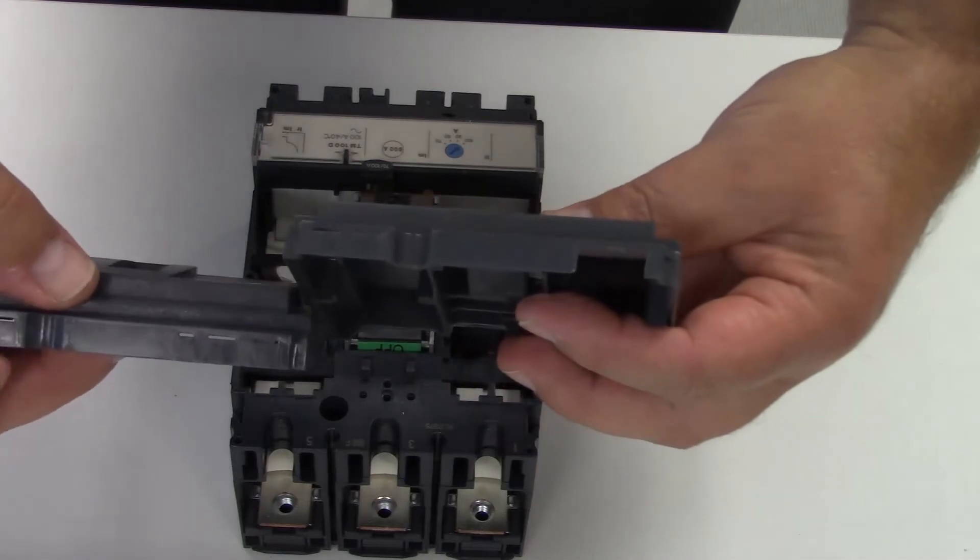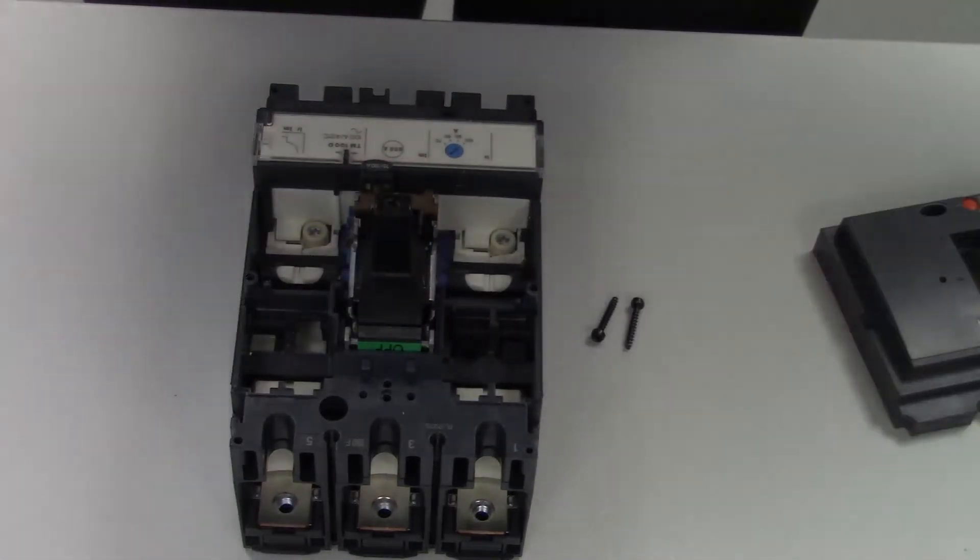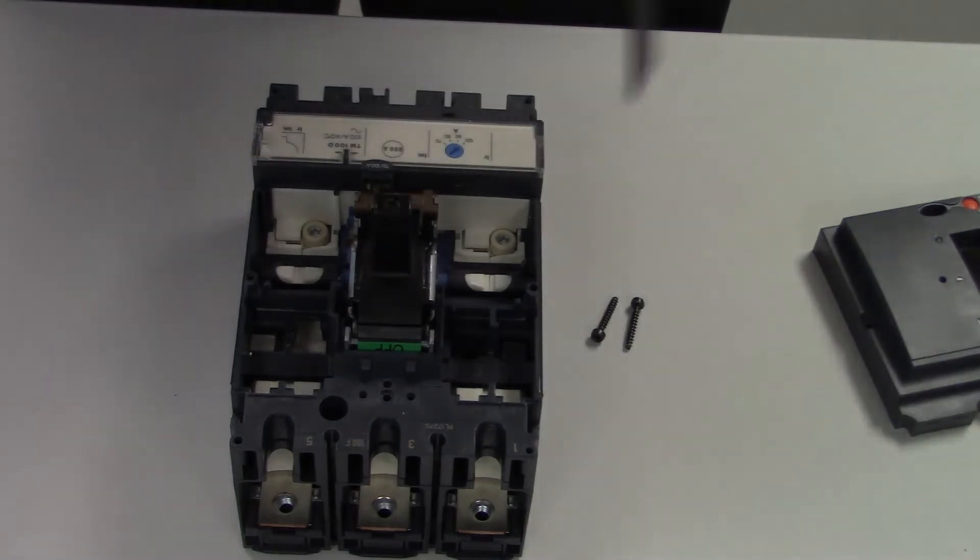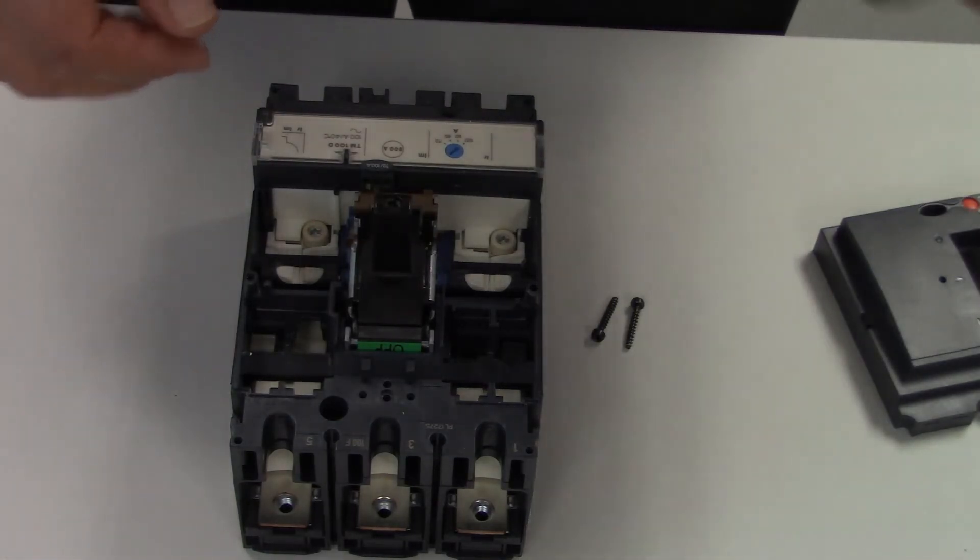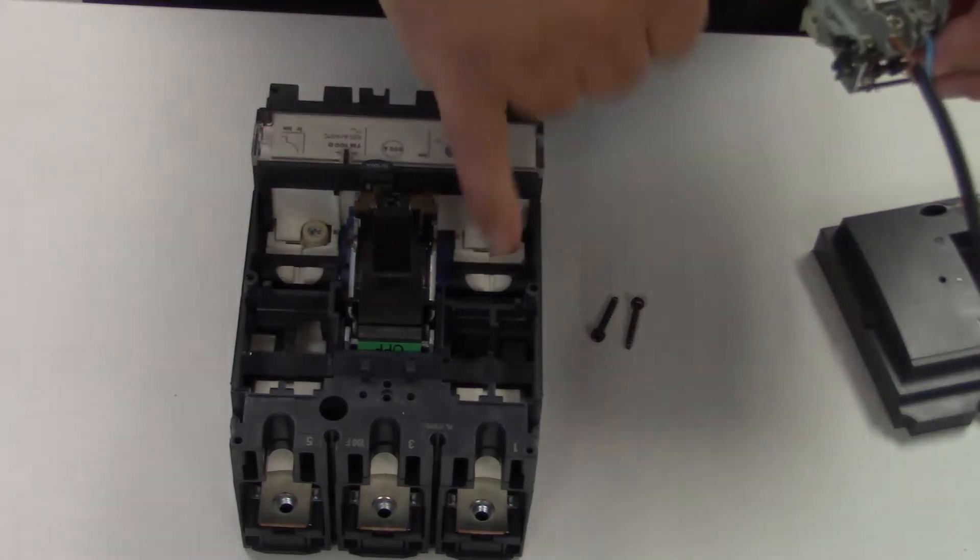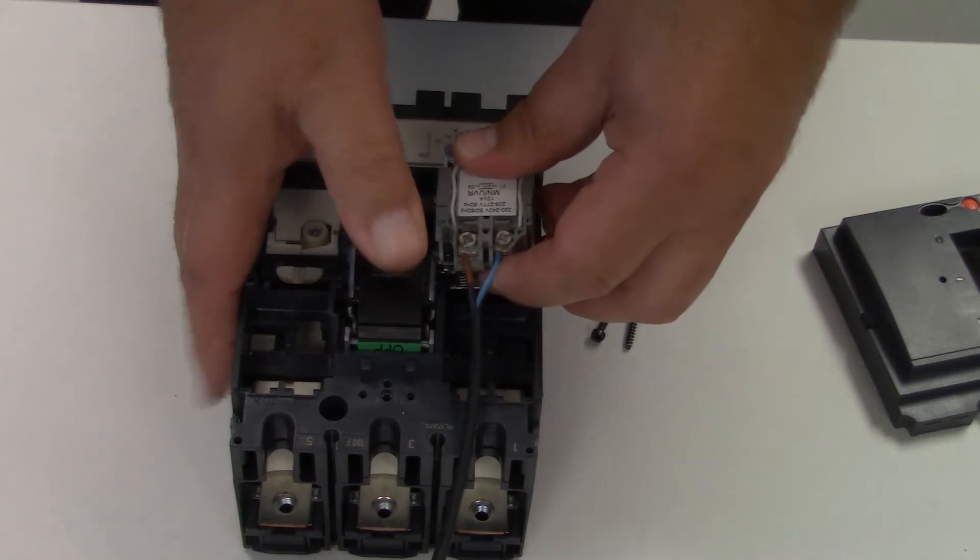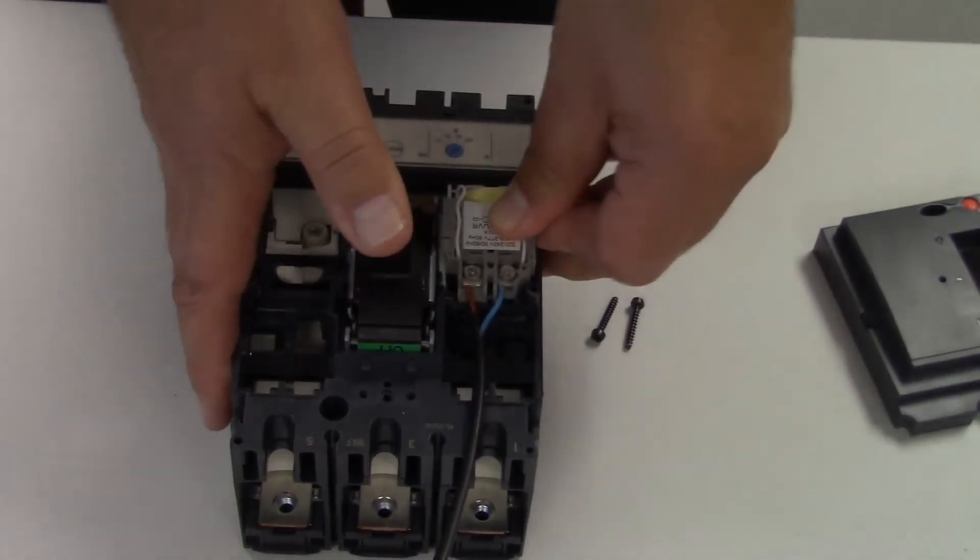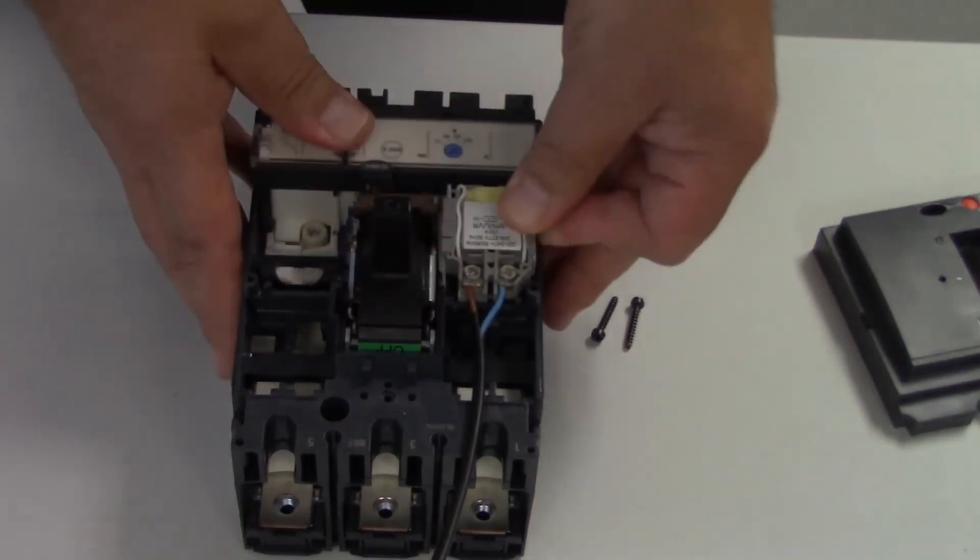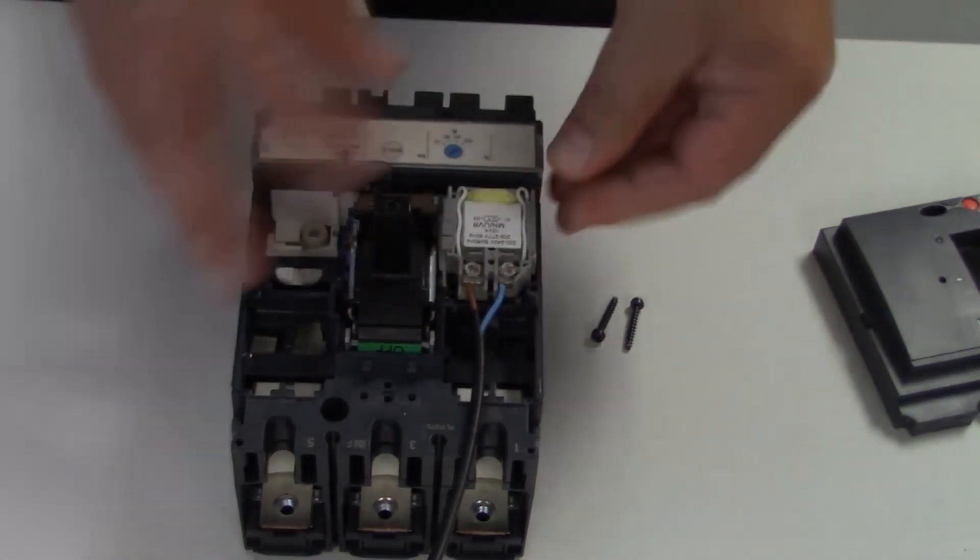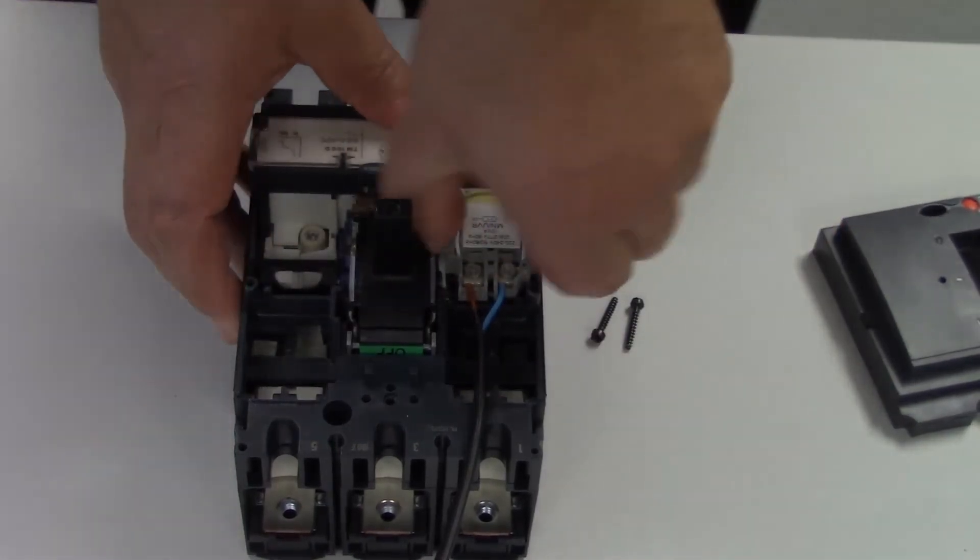With the breaker in the trip position, fit the MN or the undervolt in the bottom left hand corner. It's just a matter of wiggling the toggle and sliding the undervolt in. You'll see it clip in and it will fit flush and won't pull out—it's quite firmly fitted.